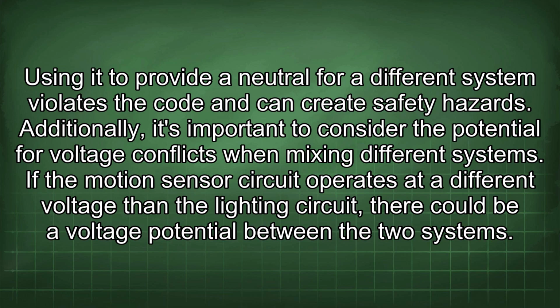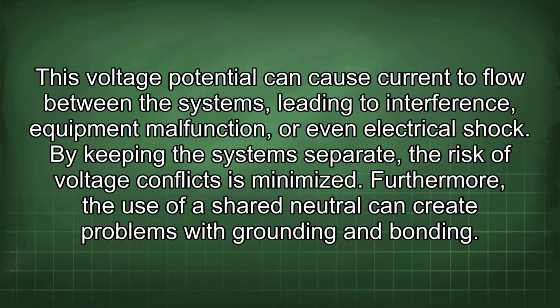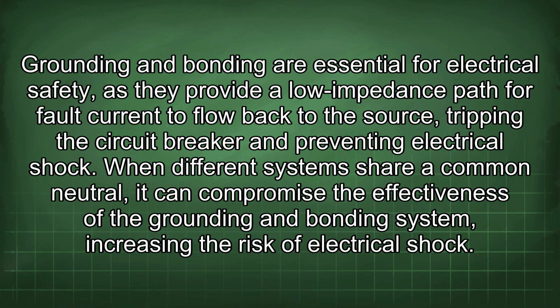Additionally, it's important to consider the potential for voltage conflicts when mixing different systems. If the motion sensor circuit operates at a different voltage than the lighting circuit, there could be a voltage potential between the two systems. This voltage potential can cause current to flow between the systems, leading to interference, equipment malfunction, or even electrical shock. By keeping the systems separate, the risk of voltage conflicts is minimized. Furthermore, the use of a shared neutral can create problems with grounding and bonding. Grounding and bonding are essential for electrical safety, as they provide a low impedance path for fault current to flow back to the source, tripping the circuit breaker and preventing electrical shock. When different systems share a common neutral, it can compromise the effectiveness of the grounding and bonding system, increasing the risk of electrical shock.